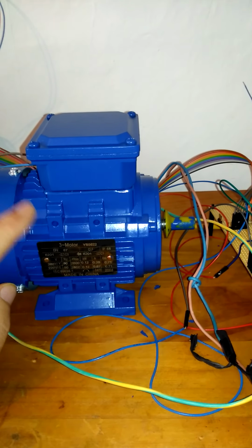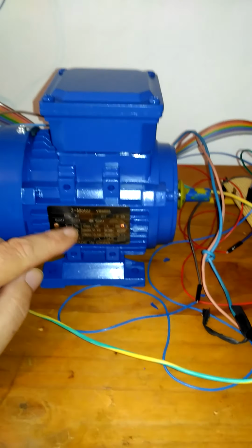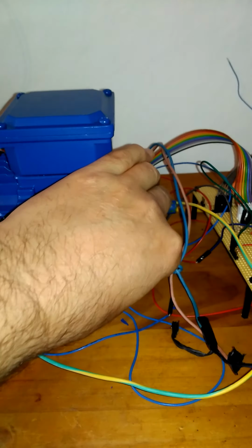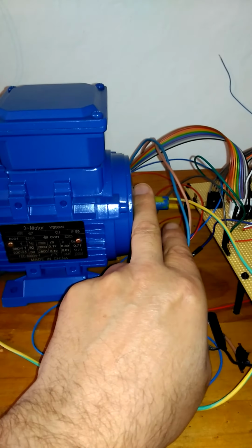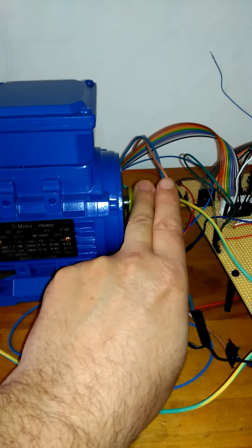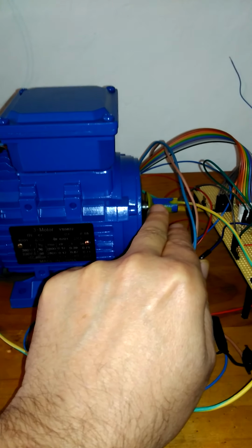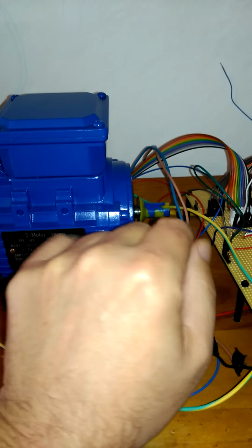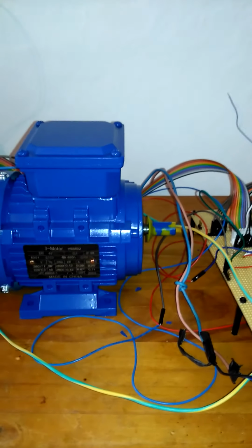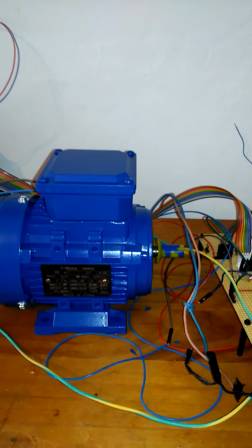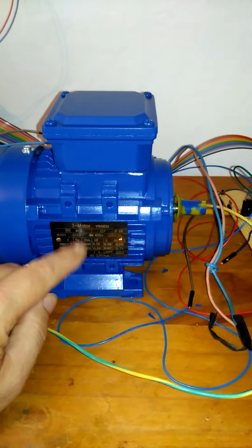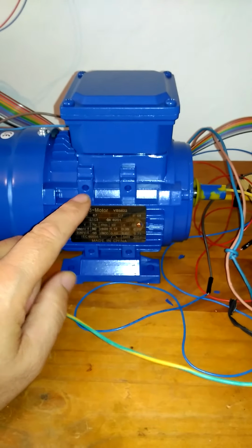This is where we're at, and the reason I'm going to do this is because this is a volts frequency algorithm. I've had that turning at 100 RPM on the volts frequency algorithm, because we have limited bus capabilities. But like I said, we want to work these parameters up because we want to use more sophisticated algorithms. We're going to use a field-orientated control or direct torque control algorithm, and we need to get the motor parameters. These are not typically given on the nameplate, or certainly not on this motor.